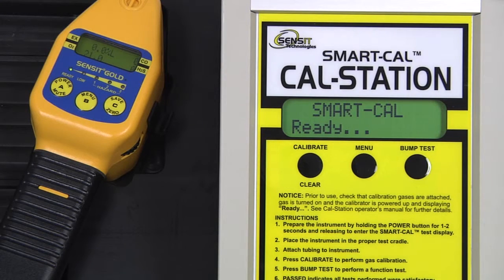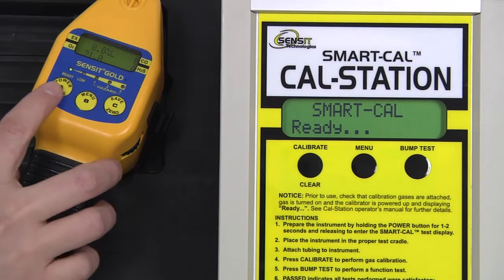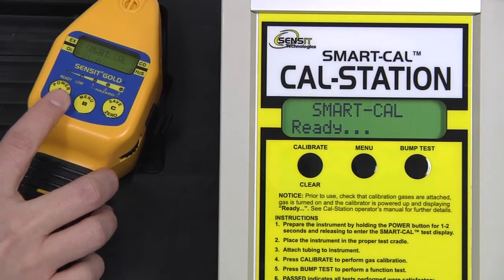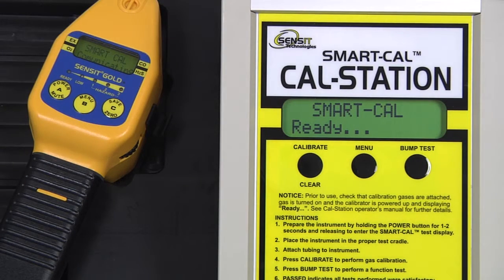After the instrument has completed its warm-up process, place the instrument in the cradle of the cal station, attach the instrument hose to the end of the gooseneck, and enter into the SMART-CAL mode by pressing and holding the A button for approximately 2 seconds. On the cal station, press and release the calibrate button, and the calibration process will begin.